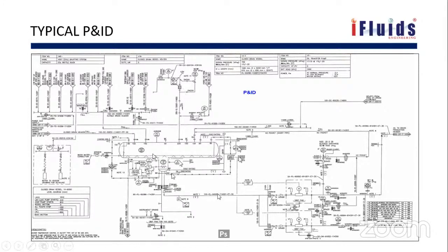So you'll see the instruments there, level gauges, the level measurements given here, and how this level measurement is connected to the level control. You see logic here, instruments, basically given in dotted lines, control schemes. So this level basically is controlled by this equipment. So that is given.